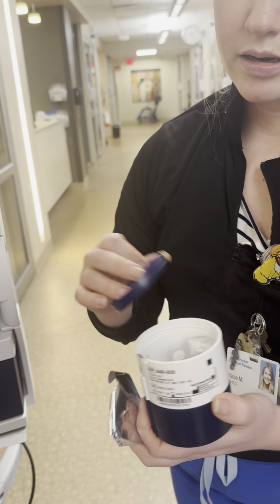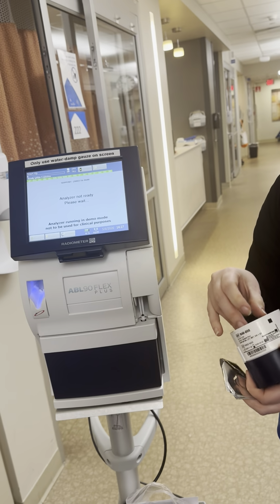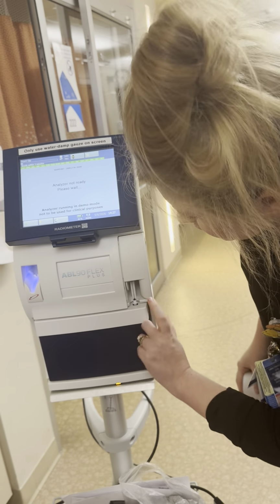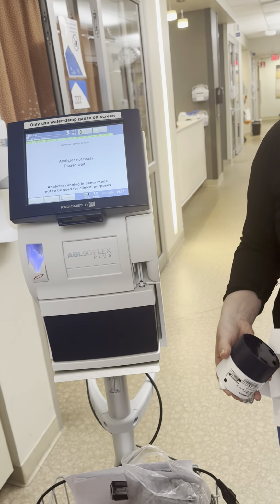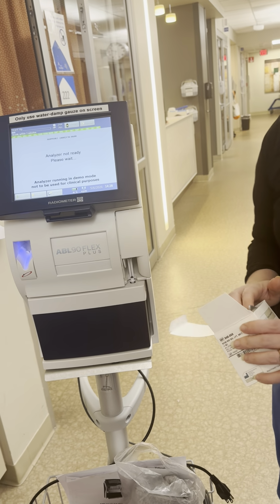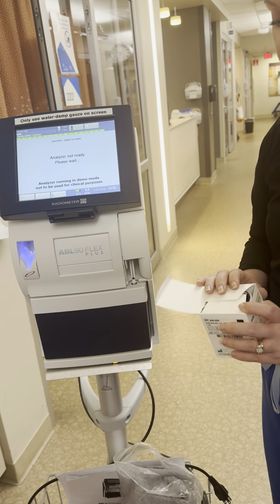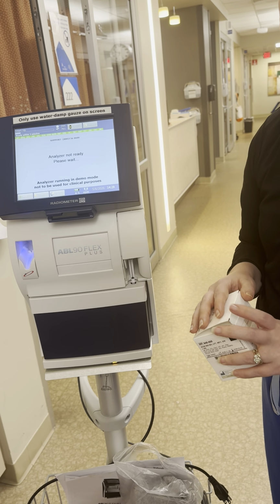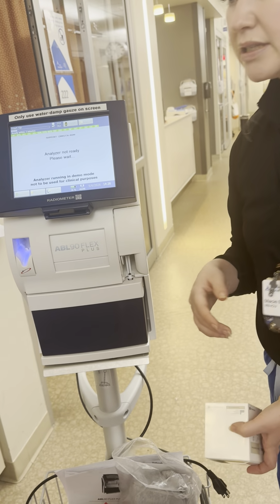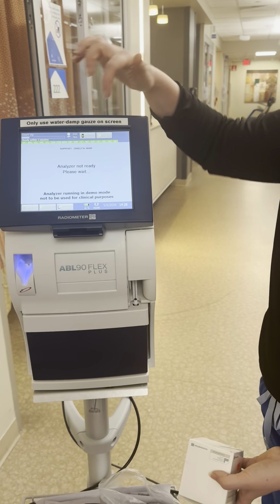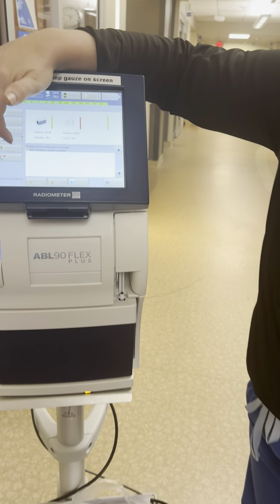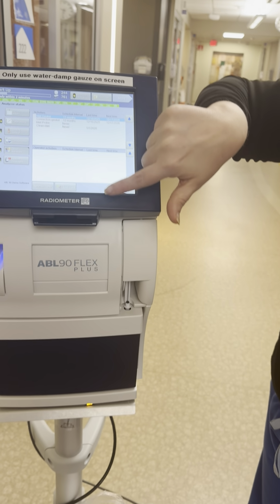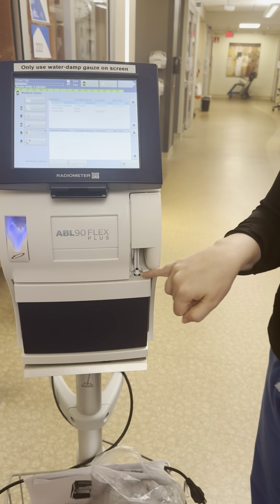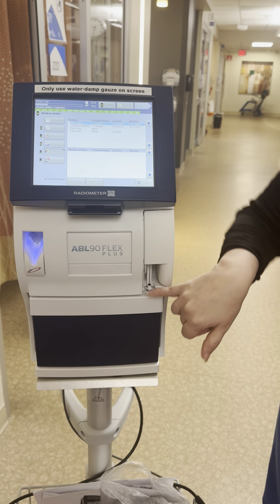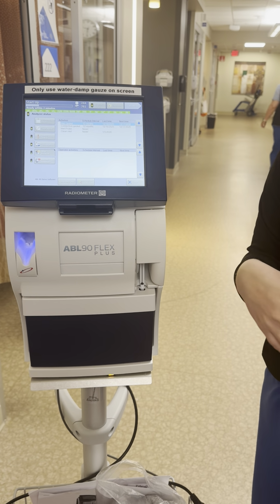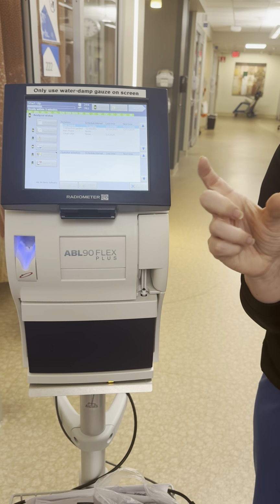The next thing is going to be your inlet probe. Right here on your probe, if we do bend it, it is not sharp, it's just a metal probe. If we bend it, it is replaceable, and we'll keep them in the team lead office. It's the same thing. It's very simple. You'll hit that you're replacing your inlet probe. Anytime we're going to address the inlet probe, it's going to be under your other activities. It's going to ask you to do a full inlet check. Technically, you can replace that little metal or the rubber gasket piece. You could replace the probe, or you could just do them all at once. If we ever need to replace it, we're just going to get the ones that have it.